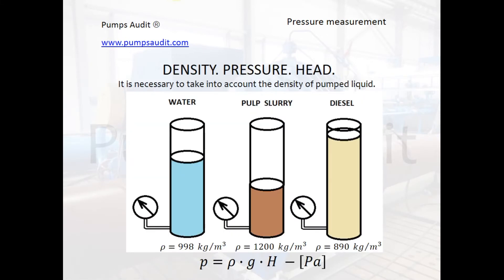When you pump a liquid that has a density different from that of cold water, it is necessary to take into account the density when calculating the head. This slide demonstrates how density influences the pressure. The pressure is the same for liquids with different densities — water, pulp slurry, and diesel — but the heads are different because of their different densities.